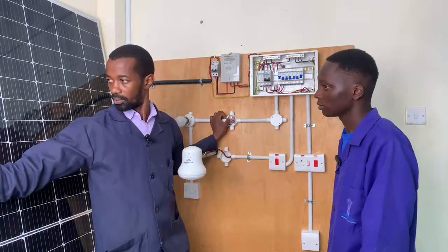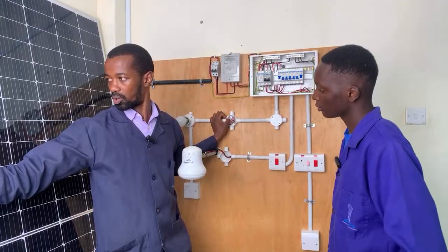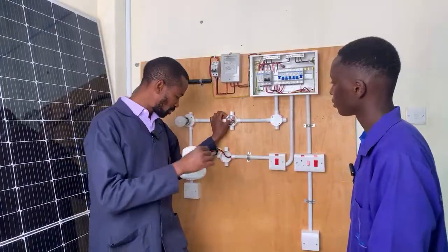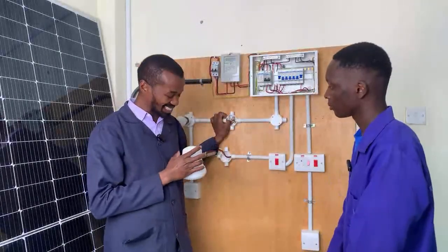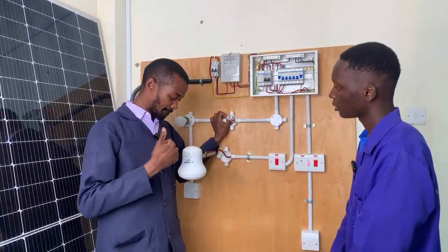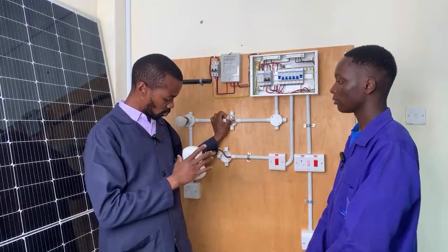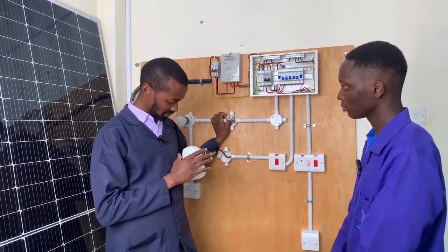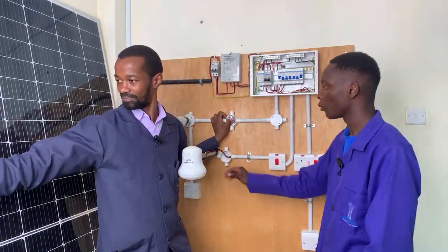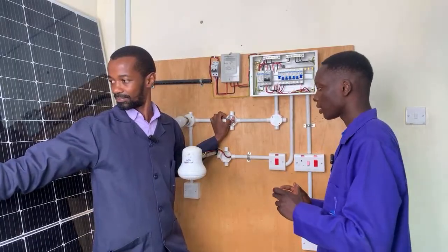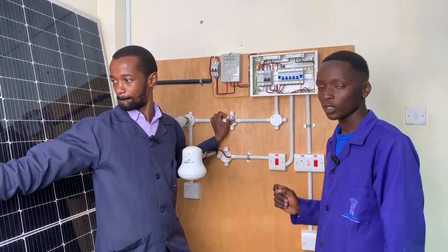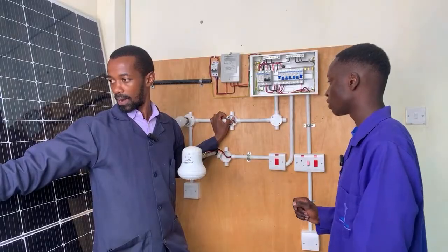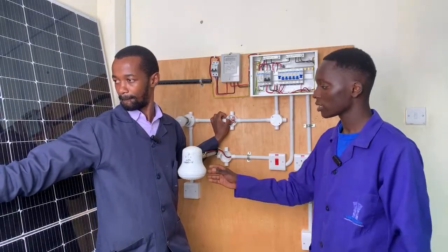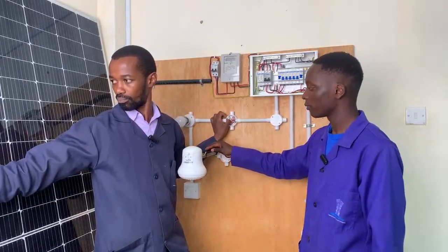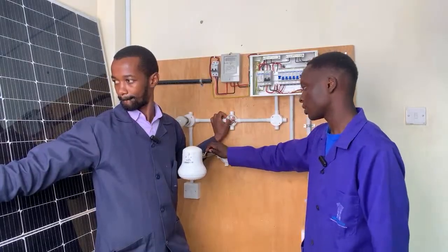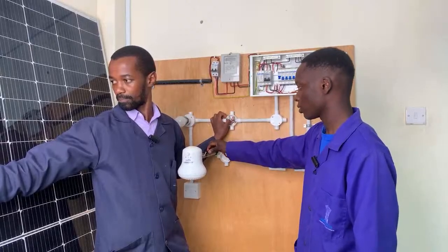Incredible. And I like that you mentioned cables, because that is very important. The size of the cable matters, because this is a heater with a heating element. The minimum size allowed for this device, what do you think? The minimum we can use is 2.5, but the rated wire to be used is 4.0 mm, because using small wires on a heating element can cause heating of the conductors, causing shocks or shorts.